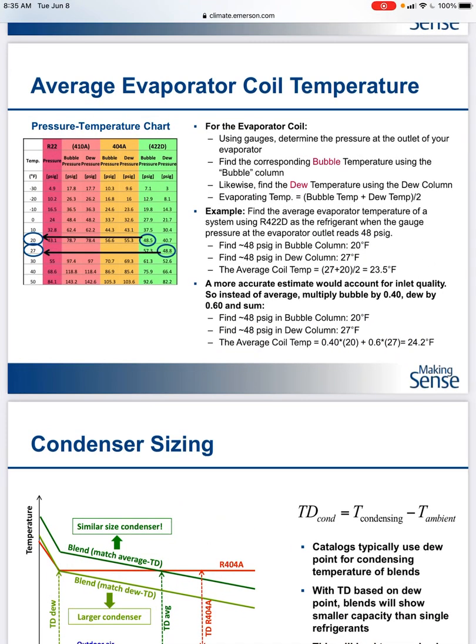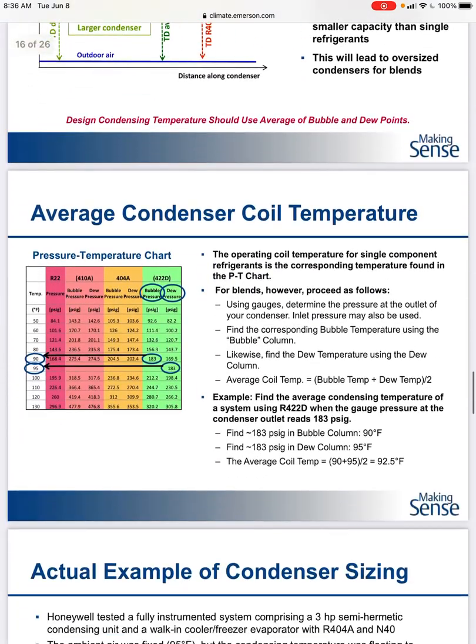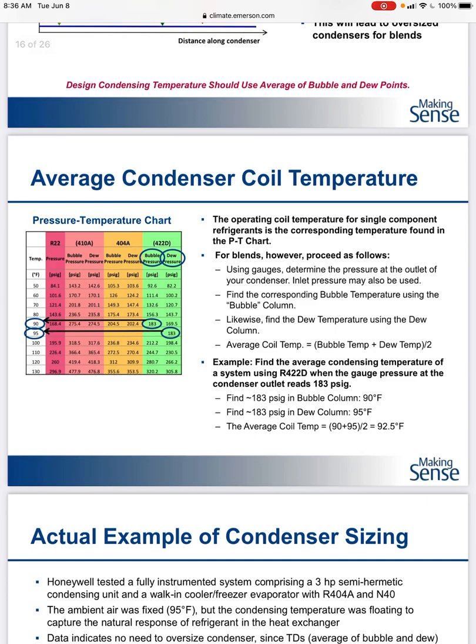This is an Emerson presentation about average coil temperature. To get the average coil temperature of a blended refrigerant, we take the pressure in the bubble point column and the dew point column at the bottom. The average coil temp is 40% of the bubble temp plus 60% of the dew point to get the average coil temperature on the evaporator side — this is because of the flash gas in the evaporator. On the condenser side, we take the bubble point plus the dew point temp divided by two to get average condensing temperature.